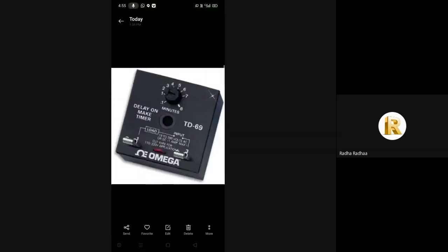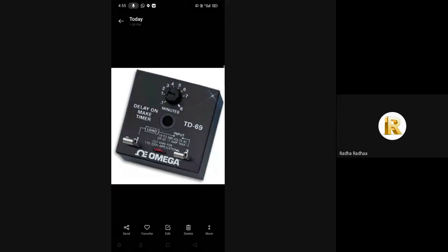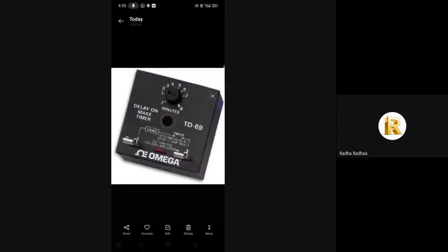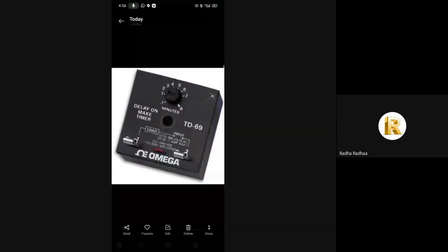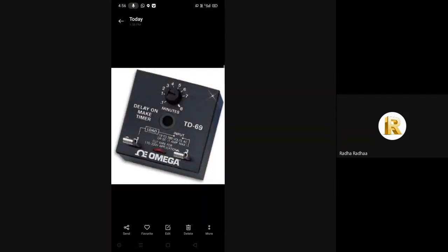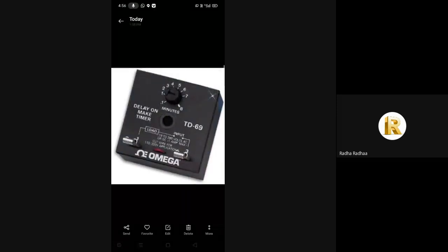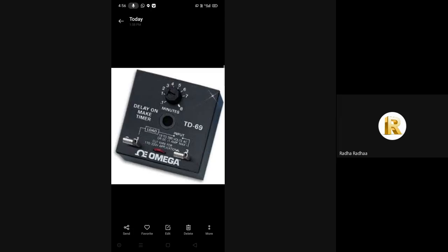The last one is time delay relay. A time delay relay is simply a control relay with a time delay built in. Their purpose is to control an event based on time. The difference between a relay and a time delay relay is when the output contacts open and close. On a control relay it happens when voltage is applied and removed from the coil. On a time delay relay, the contacts can open or close before or after some time delay.